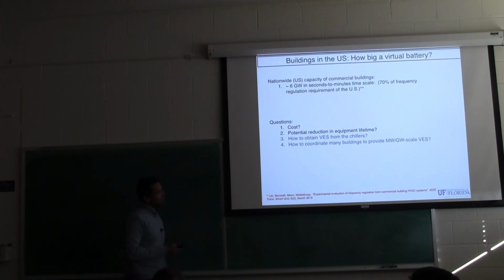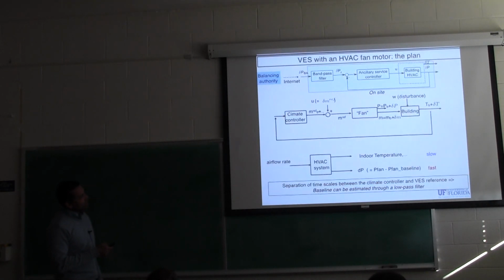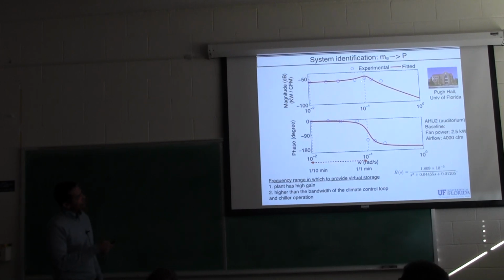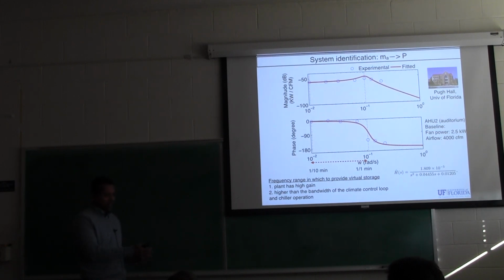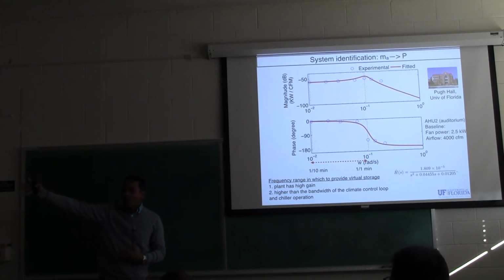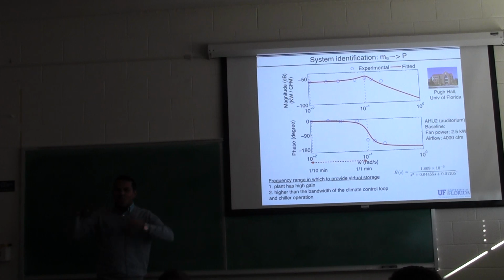That's a good point actually, because to implement this, to design this controller, we had to do this test. I guess you're right, you have to do this test for every AHU. Now maybe after like 10 AHUs, you don't need to do any more testing, because then you look at the metadata - this AHU has this kind of airflow, this big a motor, this kind of fan. These are all the possible parameters that can affect this model. If you have like 10 of these data sets, then you can probably come up with a model for the next building. If you give me the parameters of the building, how big is the motor, what is the nominal airflow, then I can figure out what kind of response I'll get, and probably don't have to redo this test. But it's a good point.